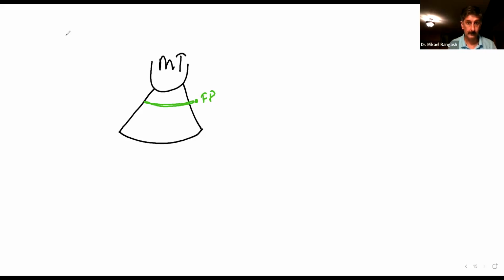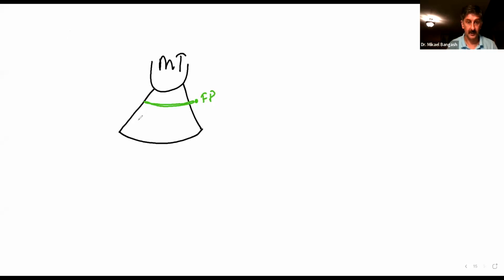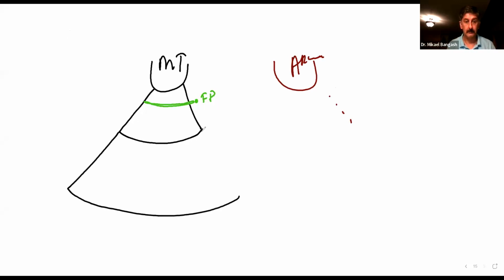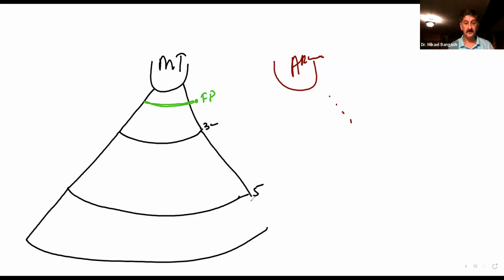Okay, just a second. Okay, good. Now, that doesn't prevent us, just because we were using a mechanical transducer, or even if we were using an annular array transducer with multiple focal points, from increasing the depth of the image. You can still take the depth of the image from, let's say, 3 centimeters to 5 centimeters, from 5 centimeters to, let's say, 10 centimeters. Is that clear?